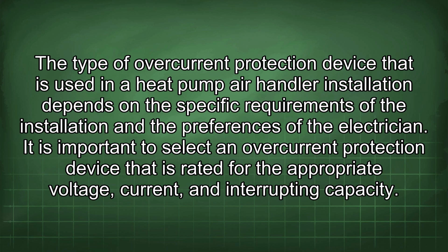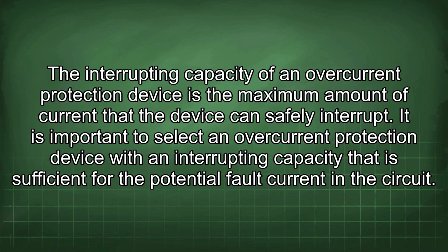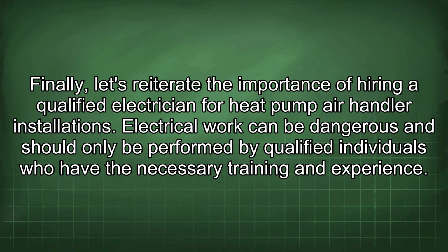The type of overcurrent protection device that is used in a heat pump air handler installation depends on the specific requirements of the installation and the preferences of the electrician. It is important to select an overcurrent protection device that is rated for the appropriate voltage, current, and interrupting capacity. The interrupting capacity of an overcurrent protection device is the maximum amount of current that the device can safely interrupt. It is important to select an overcurrent protection device with an interrupting capacity that is sufficient for the potential fault current in the circuit.